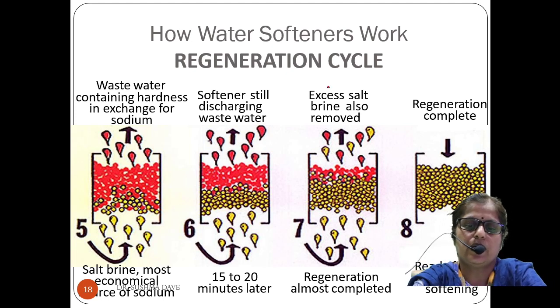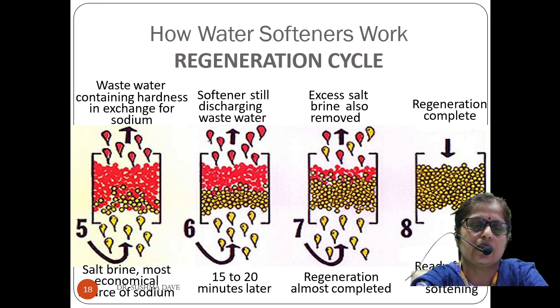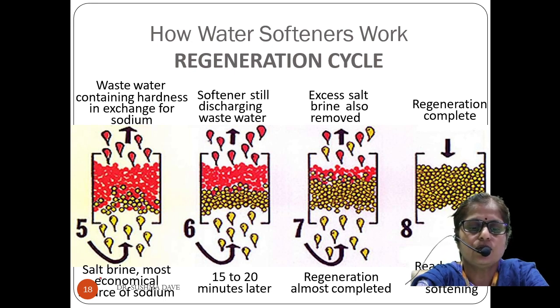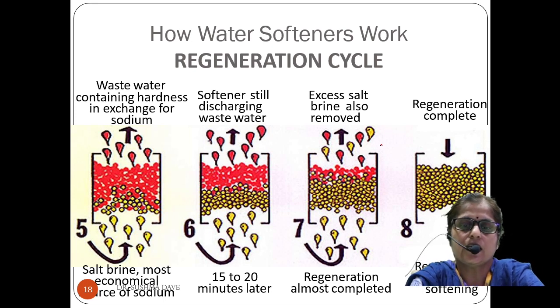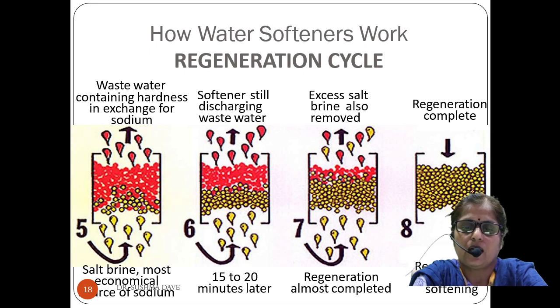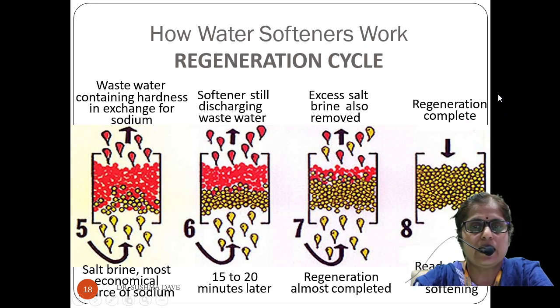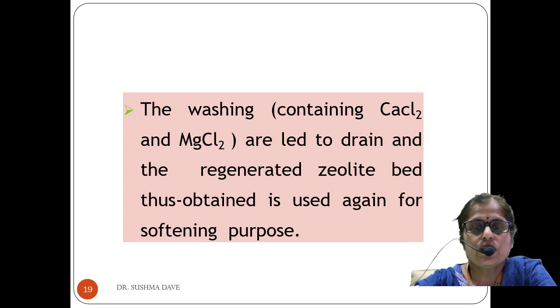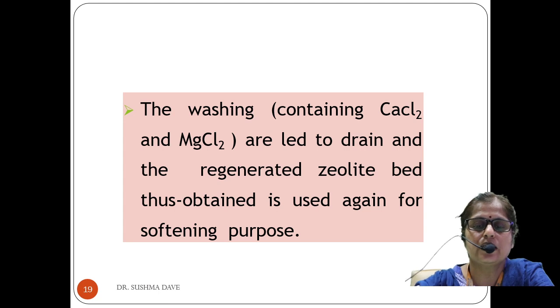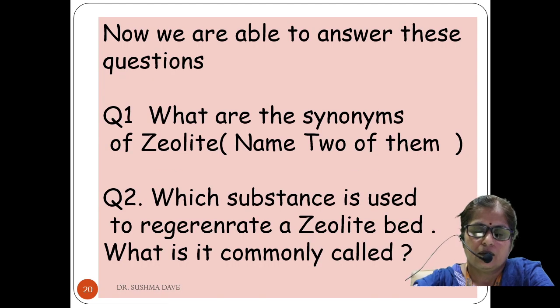In the pictorial presentation of regeneration, the red-black granular zeolite containing hardness ions is shown. Salt brine is added from the lower end, slowly regenerating all the active sites. Excess salt is also removed. After regeneration is completed, the zeolite bed is again ready for softening a new batch of water. The washings containing calcium chloride and magnesium chloride are led to drain, and the regenerated zeolite bed is reused for softening.